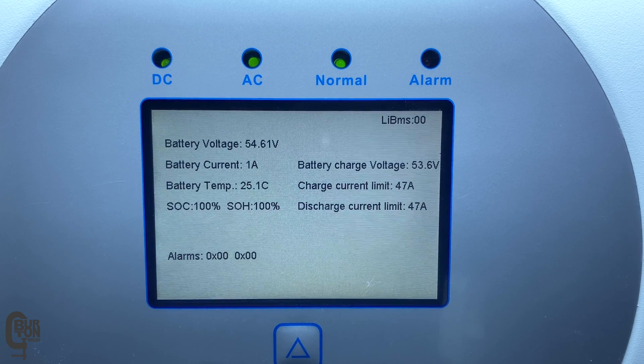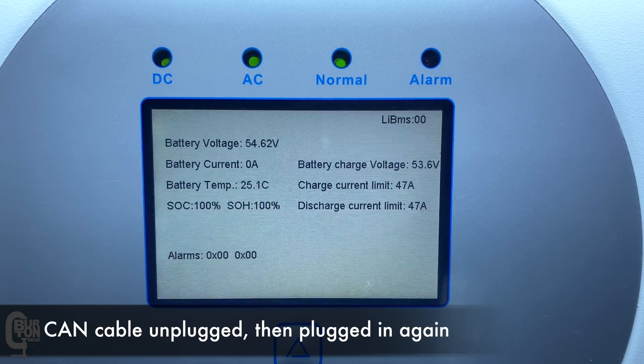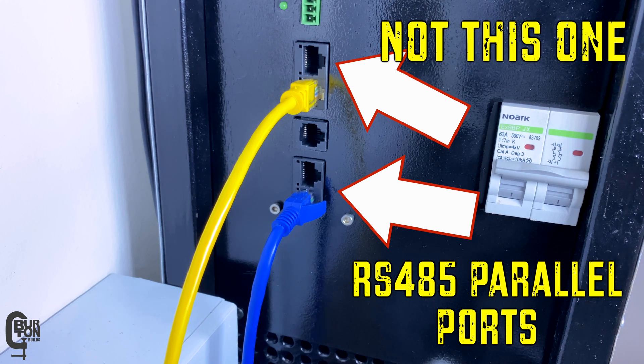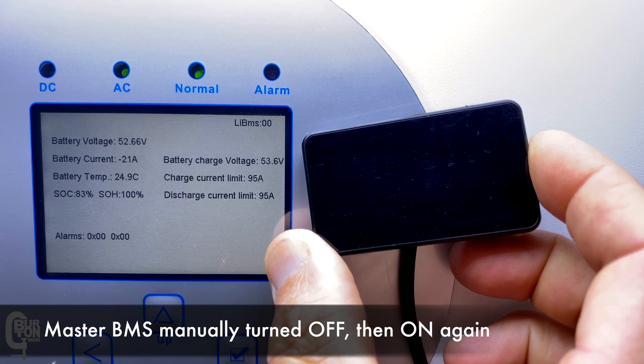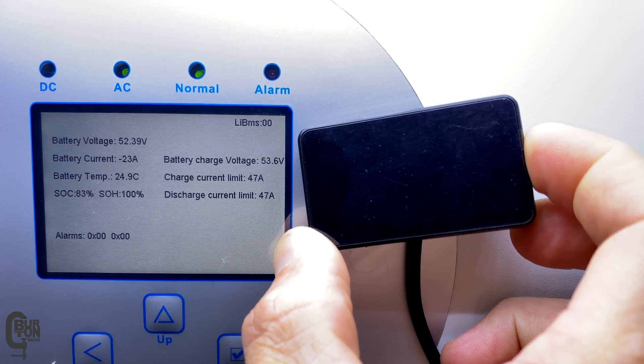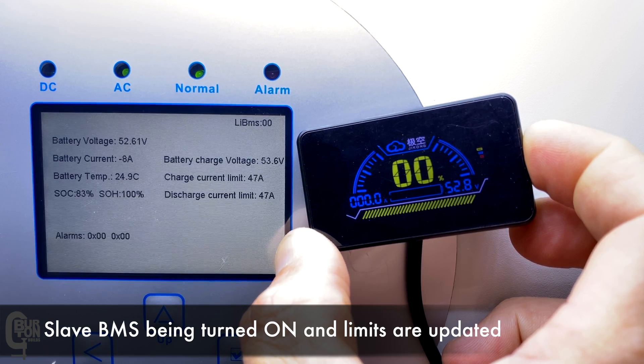Just a couple of additional notes. Number one: if your communication is lost, the LiBMS screen will look like this, but after plugging the CAN communication back in, the battery information should pop up again. Number two: for communication between two or more batteries, you need to plug the network cable into the RS-485 parallel ports on both batteries, not the RS-485 port that is next to the CAN port on the BMS. Number three: if your master BMS is turned off, then all battery communications will be lost. Number four: your charge and discharge limits displayed on the inverter screen should update according to the number of batteries installed — it adds all limits together but still deducts that five percent buffer zone.